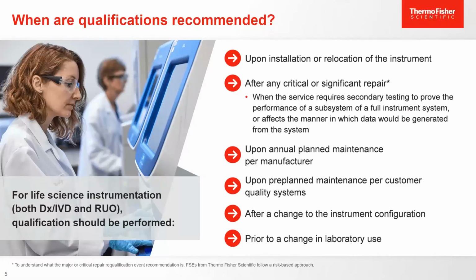When are qualifications recommended? They are recommended upon installation or relocation of the instrument, after any critical or significant repair, when the service requires secondary testing to prove the performance of the subsystem or the full instrument system, or affects the manner in which the data would be generated from the system, upon annual planned maintenance per manufacturer, upon pre-planned maintenance per customer quality systems, after a change to the instrument configuration, and lastly, prior to a change in laboratory use.